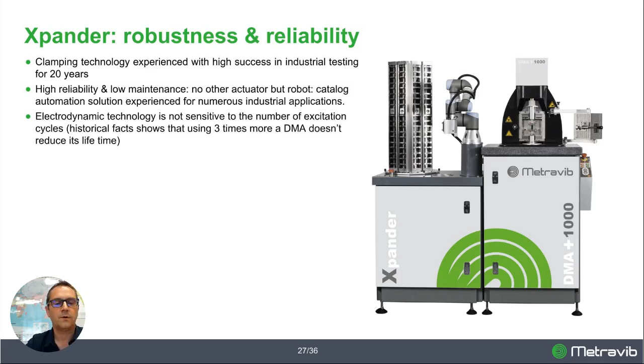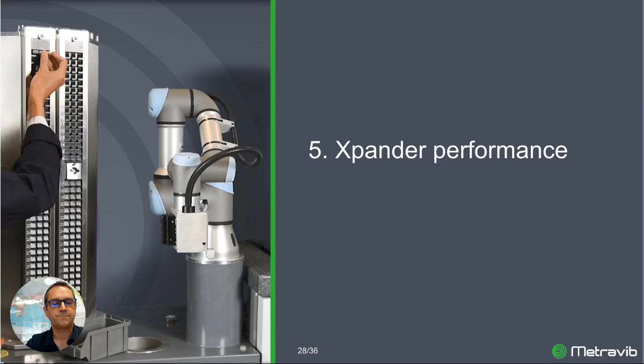And the electrodynamic technology is not sensitive to the number of excitation cycles. So it's historical facts. Using 3 times more DMA doesn't reduce its lifetime, and that's a very important feedback we get for 20 years now from the former automated range of Metravib DMA. So let's have a look at Xpander performance.